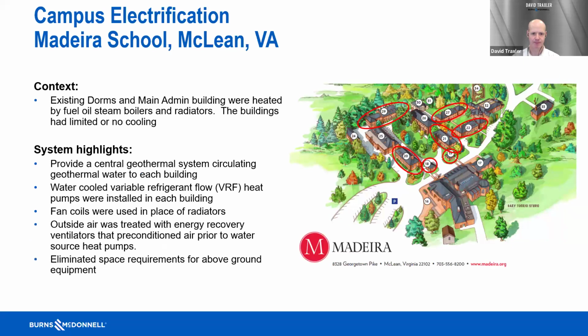This is an artistic rendering of the Madeira School campus. The buildings circled in red were part of the retrofit project, mostly dormitory buildings, though building 29 is also the head office building. Since the buildings are packed together with little open landscaping, we placed the geothermal field in a remote location in the parking lot, with a vault piping the geothermal water over to each building. Each building had water-to-water heat pumps in the form of variable refrigerant flow (VRF) systems to heat and cool using the water.